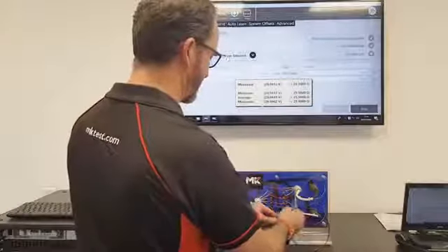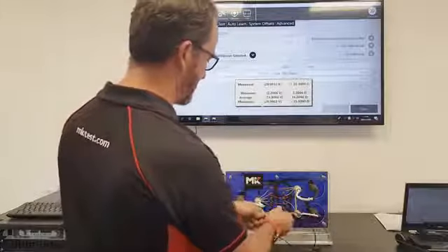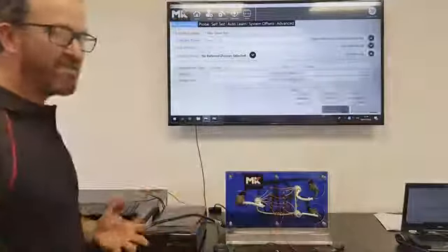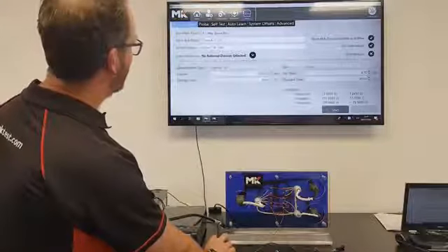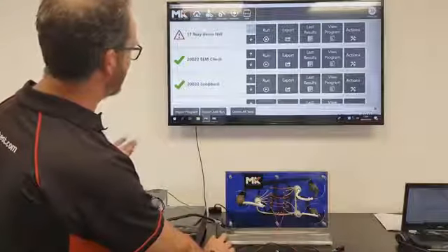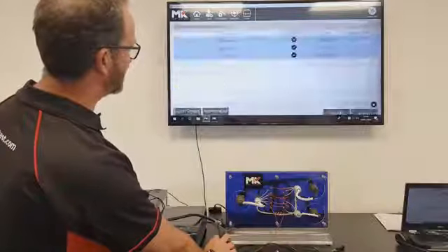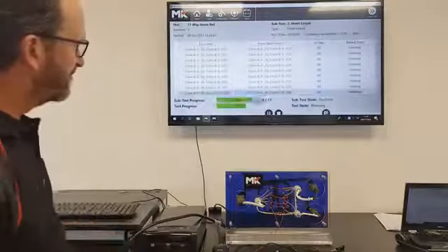And sure enough, it's at clamp voltage, open circuit. And as I close this up, you can see it's now measuring 2.3 ohms. If I remove this resistor, 1.3 ohms. It's a 1 ohm resistor. So you can see a very useful diagnostics tool that means you don't have to run complete programs. When I go back home, you can see here that the program failed last time I ran it. If I go to run this test, having fixed that issue, I now have a good test.